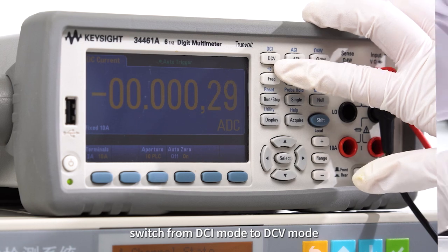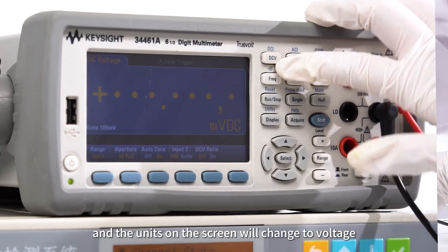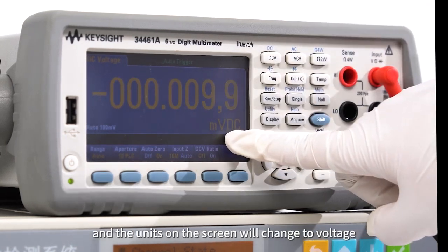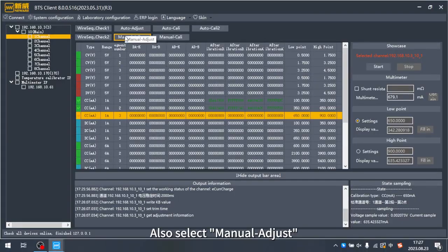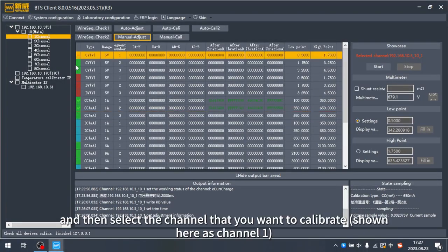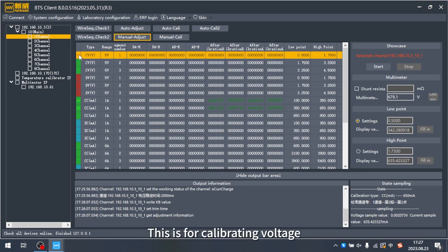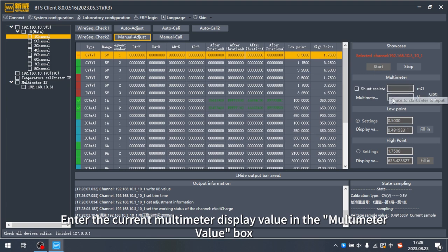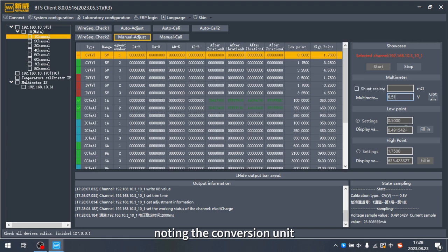Next, switch from DCI mode to DCV mode, and the units on the screen will change to voltage. Also select Manual Adjust, and then select the channel that you want to calibrate, shown here as Channel 1. This is for calibrating voltage, so double-click the CVV option. After successful selection, a yellow arrow is displayed before the option.